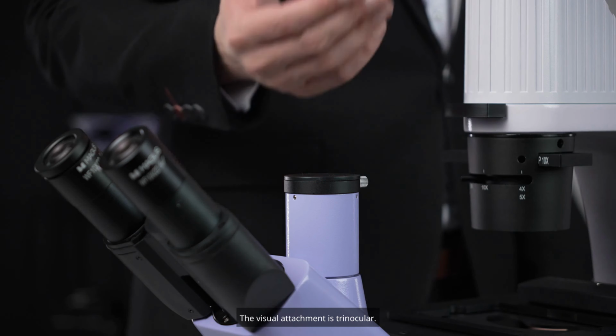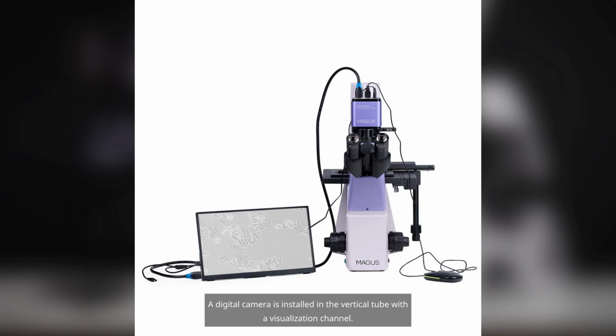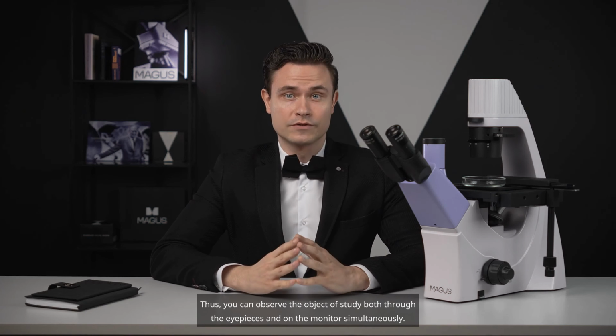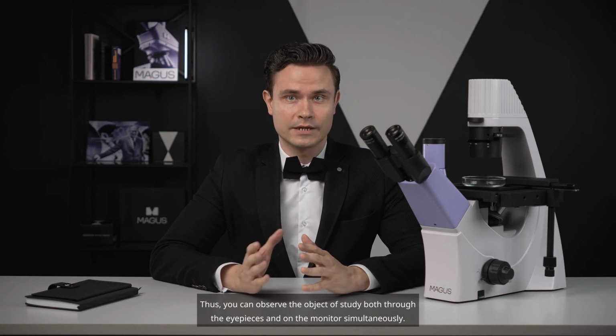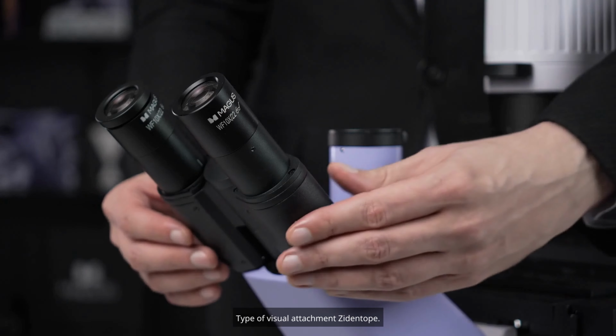The visual attachment is trinocular. A digital camera is installed in the vertical tube with a visualization channel. The division of the light beam is constant, without switching. 50% of the light goes to the eyepieces, and 50% to the visualization channel. Thus, you can observe the object of study both through the eyepieces and on the monitor simultaneously. Type of visual attachment: Siedentopf.